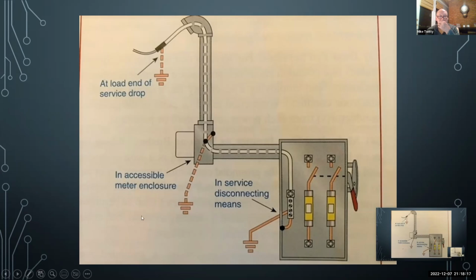In the jurisdictions where I live, our utilities require that the grounding electrode conductor land in the meter base. That's not what the National Electrical Code requires, since it allows these three, but the utility says we want all the grounding electrode conductors to land in the meter base. A lot of jurisdictions typically have them in the service equipment. They can be at any one of those three places.